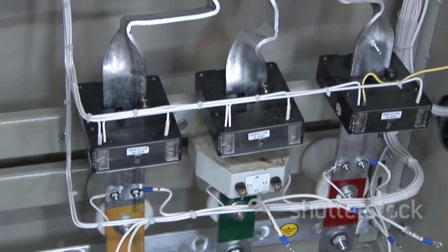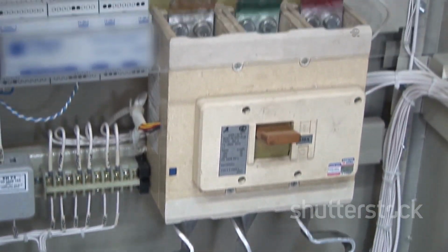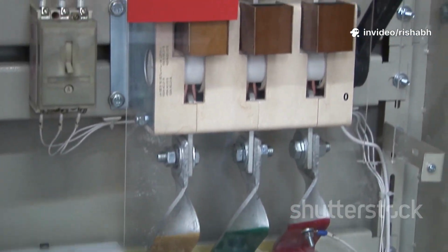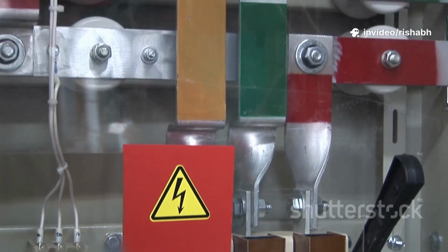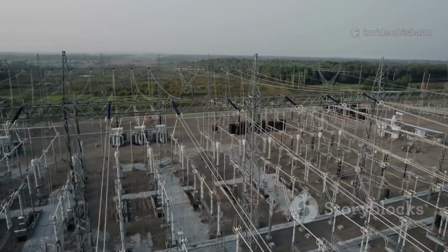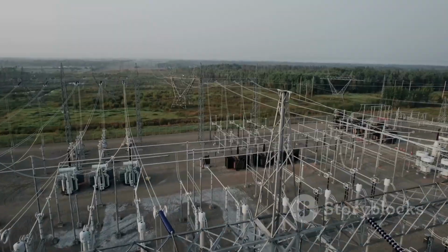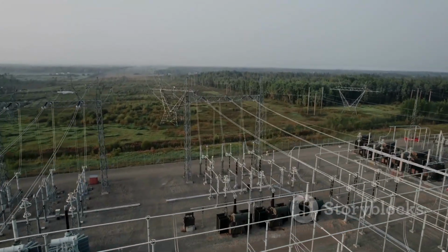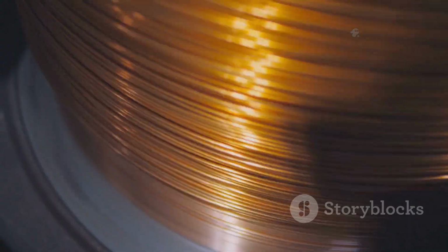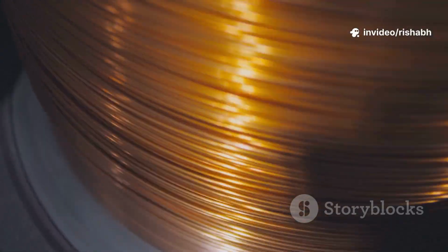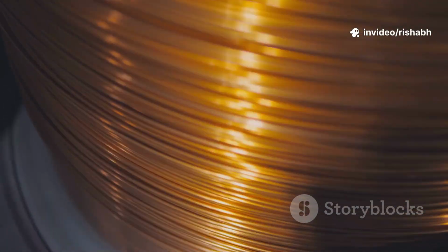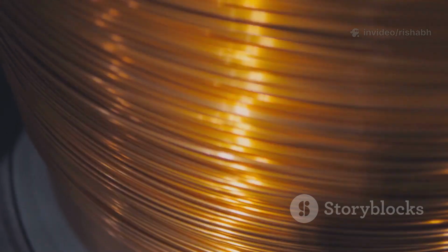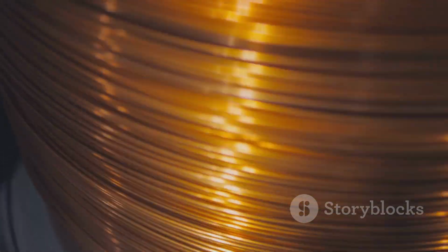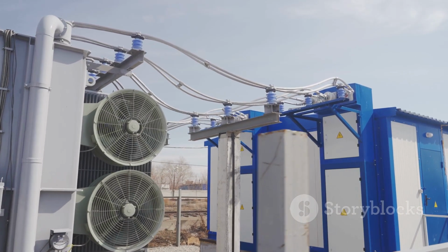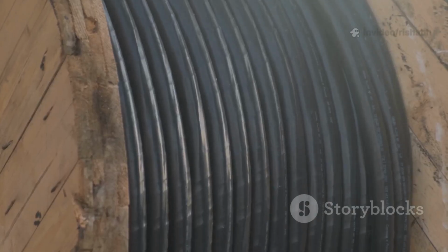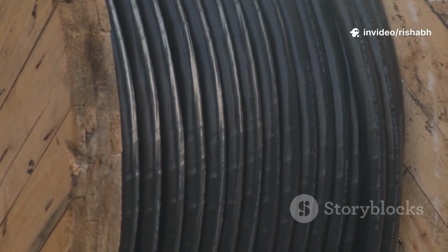For structural support, and to create barriers between winding layers and sections, a denser material called pressboard is used. It is essentially a thick, rigid cardboard, also made from pure cellulose, designed to withstand electrical and mechanical stress. Different types of windings are used depending on the voltage and power rating. For lower voltages, simple helical or disc windings might be used. For the high-voltage windings of large power transformers, interleaved disc or continuous disc windings are common.